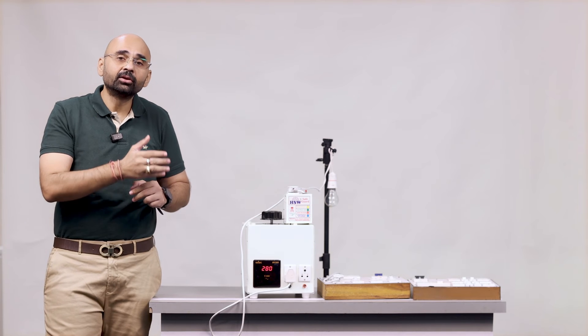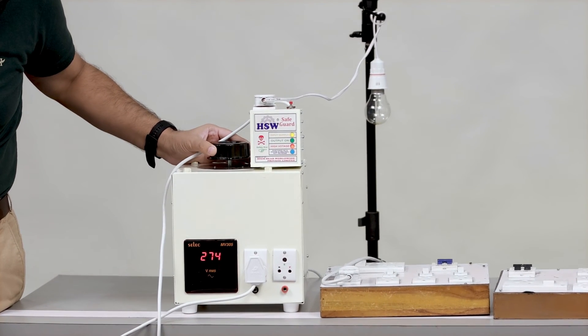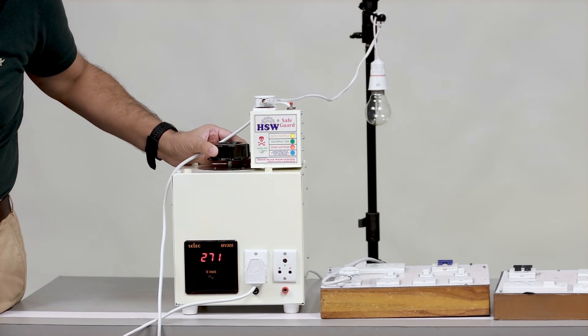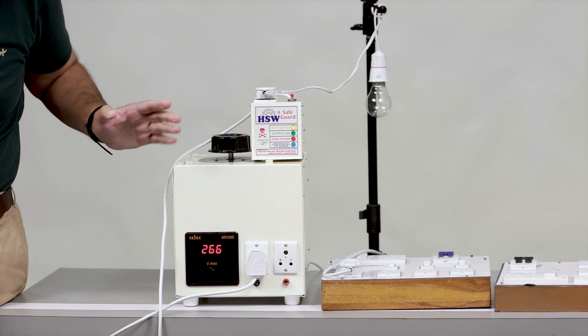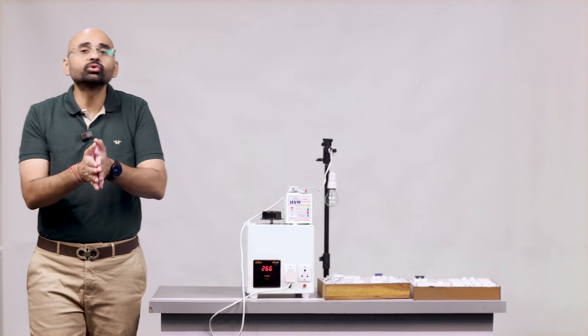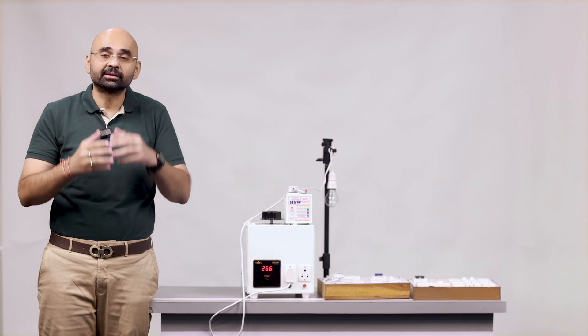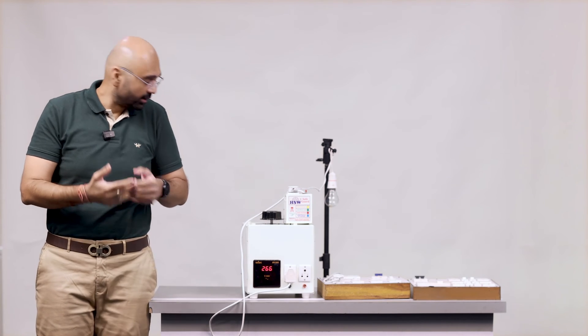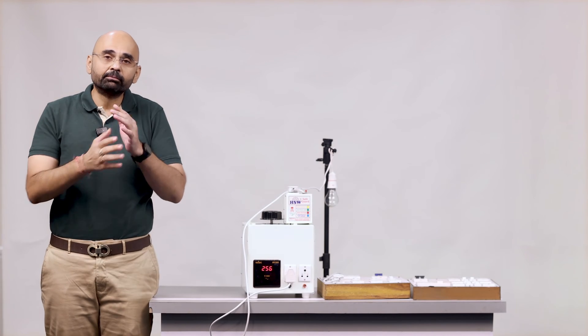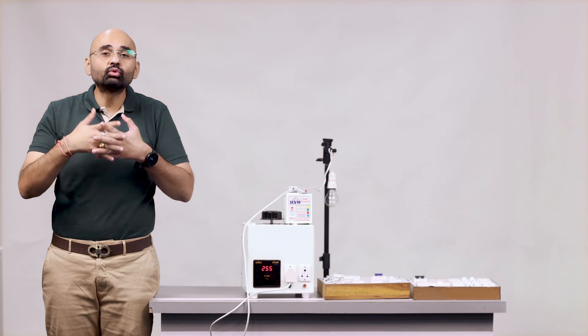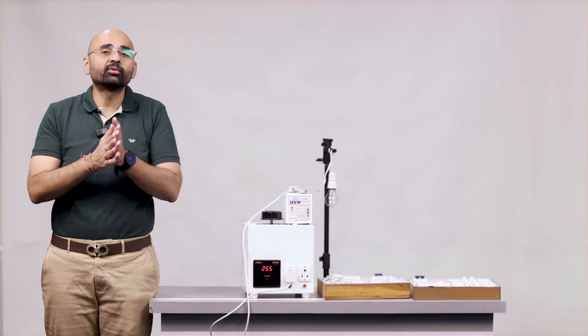So now we will gradually lower down the voltage. So as soon as it comes to 266, means now the voltage is in such condition that your electric appliance can be usable. So now you can see that high voltage light is off but device will take two minutes to further supply the electricity. So now we have to wait for two minutes.